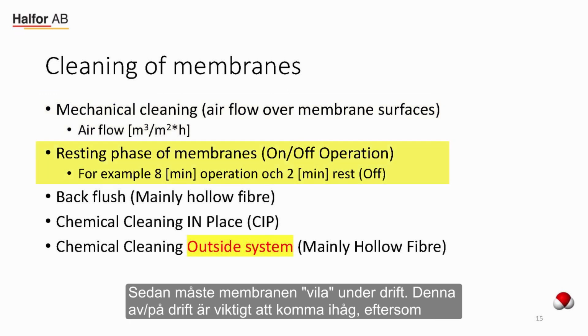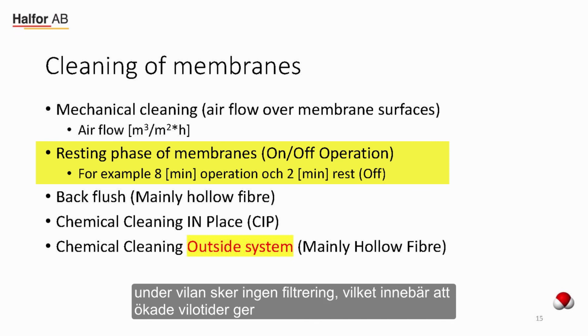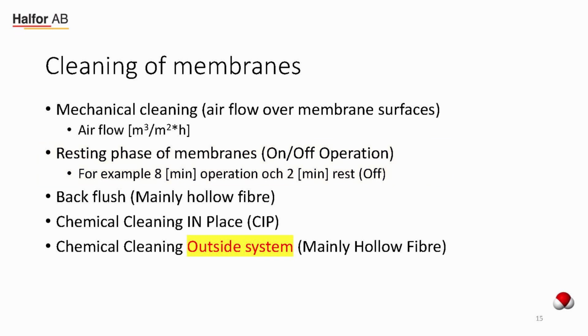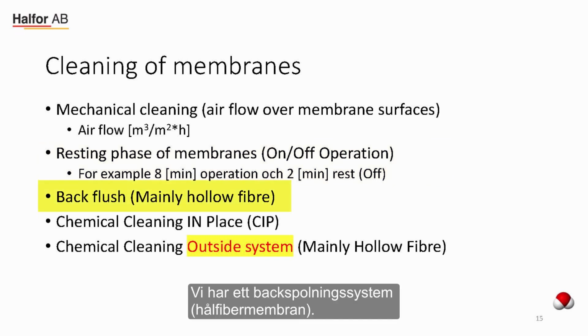Then you have a resting phase of the membranes. Basically, you shut on and off during operation. And here is a very important thing to remember, that during the resting phase, no filtration is done. So when you design or work with the membrane system, you need to take into account the downtime during normal operation for the membranes. Then you have a backflush system, which is mainly for hollow fiber.